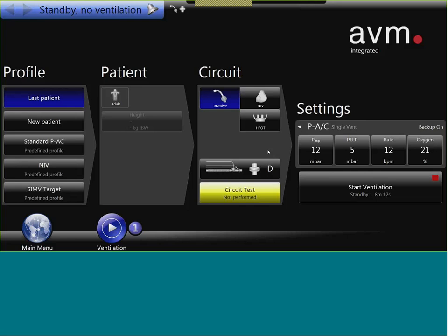If you use active humidification, we recommend for the protection of the ventilator to have a filter at the inspiratory outlet, because if some humidity or fluid from the chamber goes up into the ventilator, just behind that inspiratory outlet there is directly the inspiratory block and the inspiratory valve.